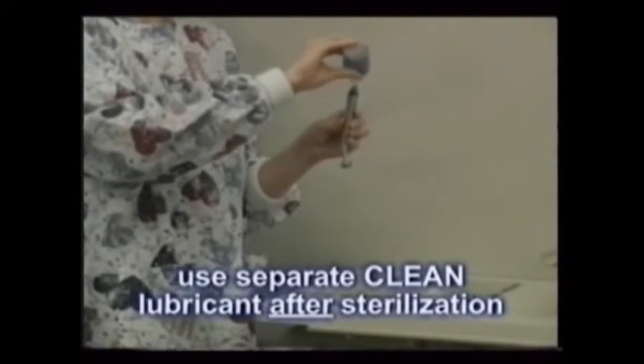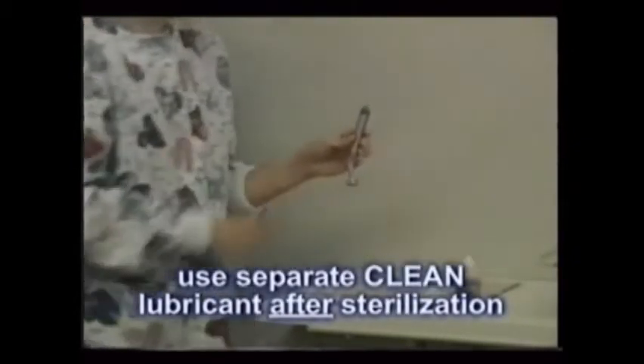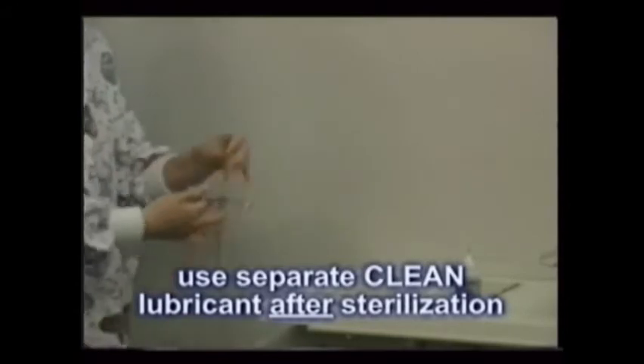Remember to use a different, clean lubricant after removing the handpiece from its sterile package and just before attaching it to its air hose. A drop of oil is placed in the slow-speed motor and on the gear of each slow-speed attachment after every autoclave procedure.